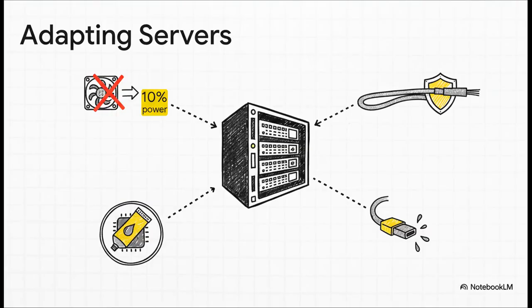To get standard off-the-shelf servers ready for life underwater, or under oil, they had to make key changes. The biggest was yanking out all the internal fans, which saves about 10% of the server's own power consumption. Then things like the thermal grease on the processors and even the standard cables had to be swapped out for special oil-compatible versions to ensure reliability for years.